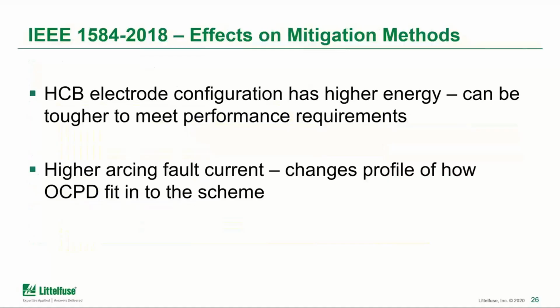Now, when you look at some of the changes, what effect does that have on the mitigation methods, or how you might choose to mitigate? First and foremost, that horizontal electrode configuration has a higher energy level, and so that can make it more difficult to meet some of the performance requirements depending on what mitigation method you're choosing. It's also good to be aware that there are some higher arcing fault currents with the formulas, and that can change the profile of how your overcurrent protection devices will fit into the scheme and will coordinate. In some cases, it actually makes them provide better interrupting just because of the high current.